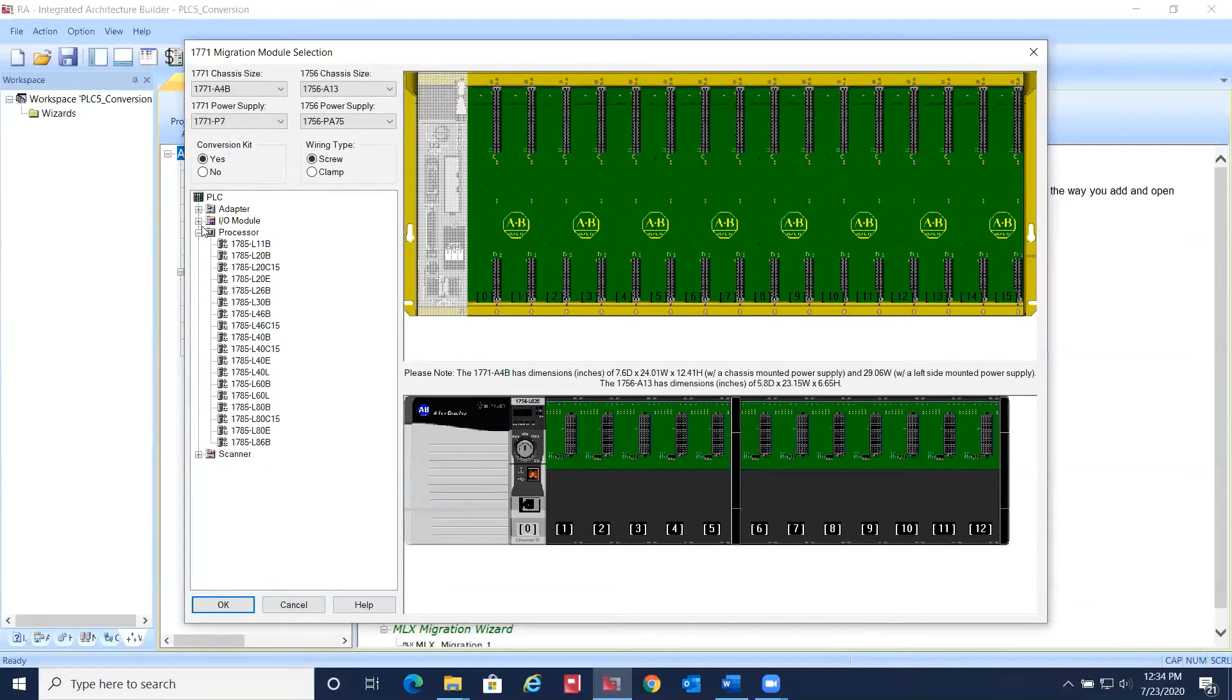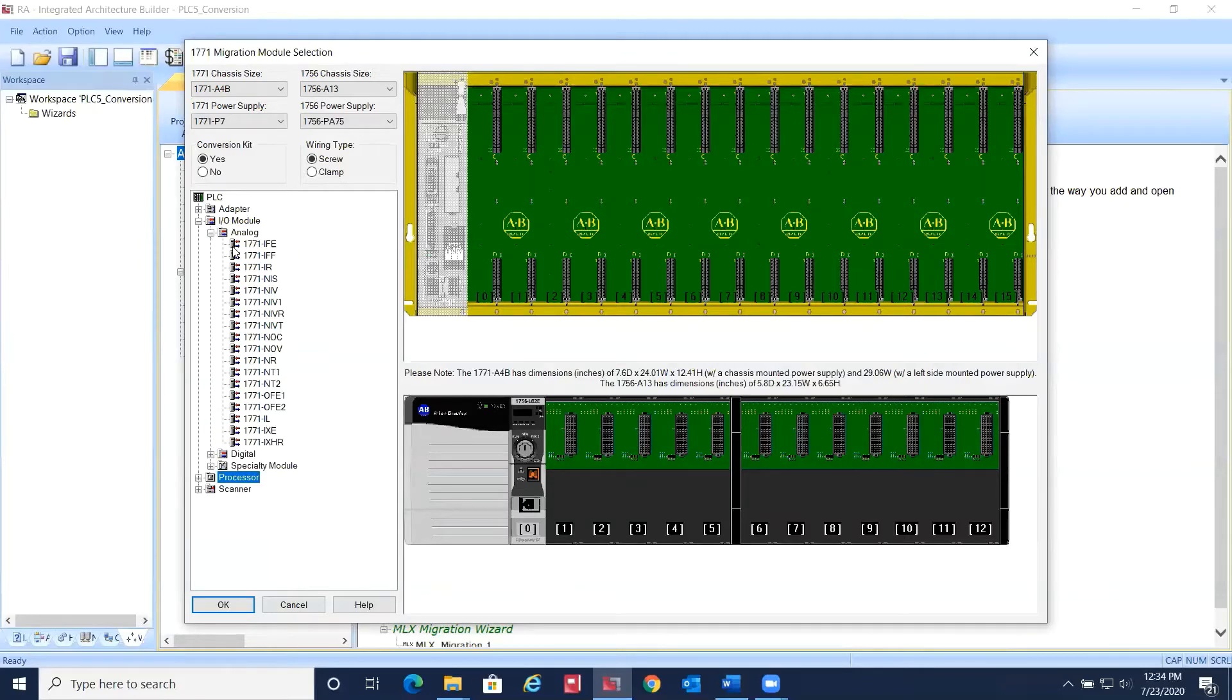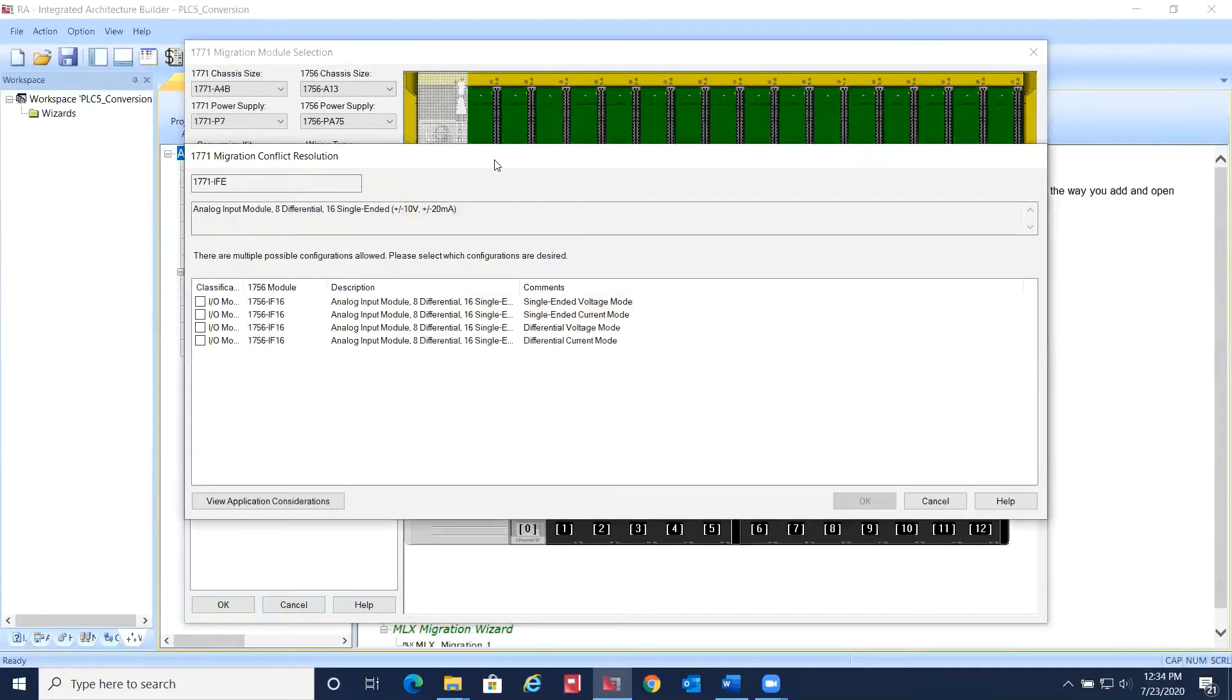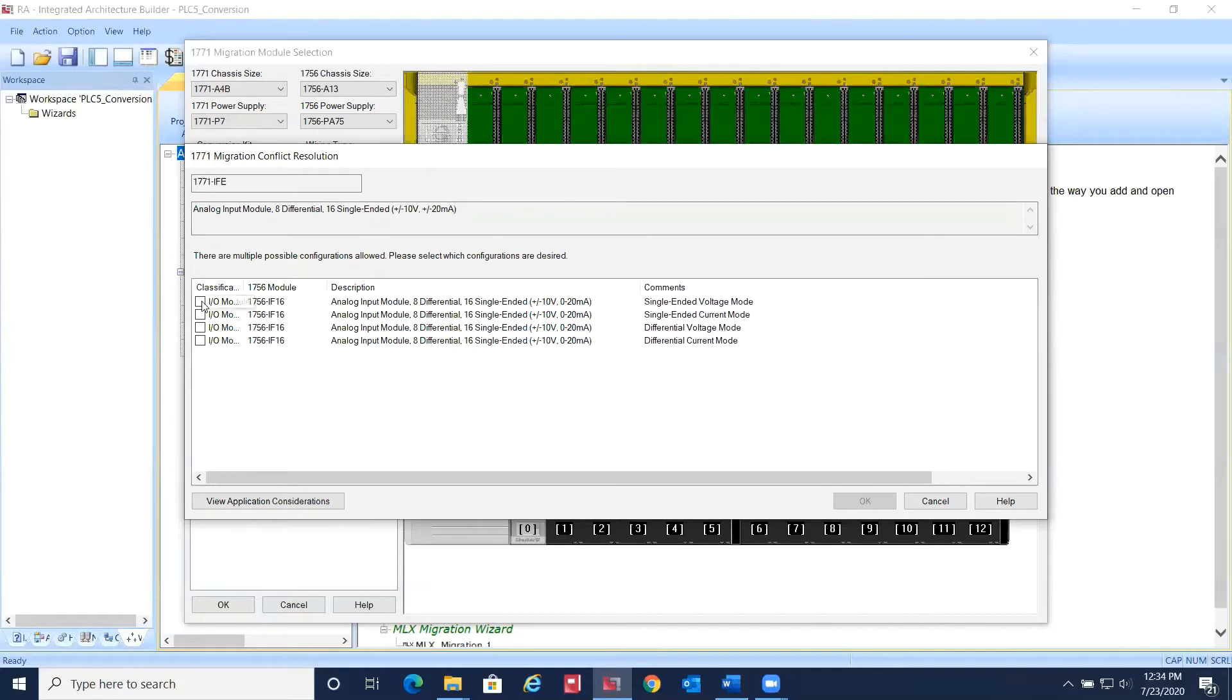Now simply drag and drop the I/O modules in the order that they exist in the current PLC5 chassis. IAB will automatically select the appropriate ControlLogix card based on the specifications of the PLC5 I/O module.